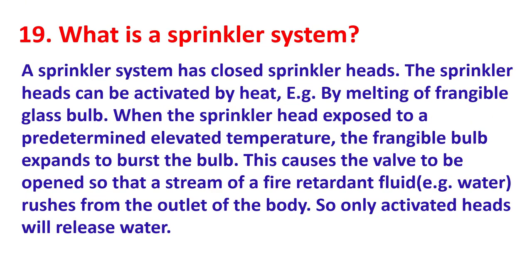What is a sprinkler system? A sprinkler system has closed sprinkler heads that can be activated by heat — for example, by melting a frangible glass bulb. When the sprinkler head is exposed to a predetermined elevated temperature, the frangible bulb expands and bursts. This causes the valve to open so that a stream of fire-retardant fluid such as water rushes from the outlet. Only activated heads will release water.